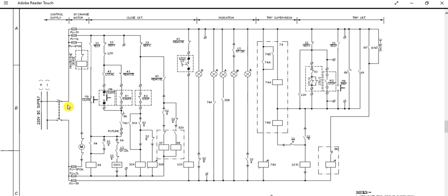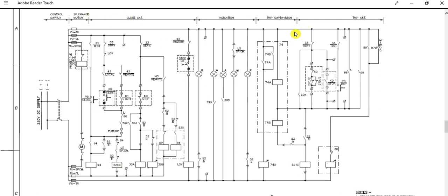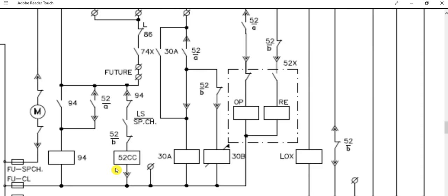This is the spring charging motor circuit — the motor is also operated by 220 volt DC. This is the motor protective device. This area is the closing circuit portion, this area is the indication circuit, this area is trip circuit supervision, and lastly here is the trip circuit. The main parts are the closing circuit and the tripping circuit.